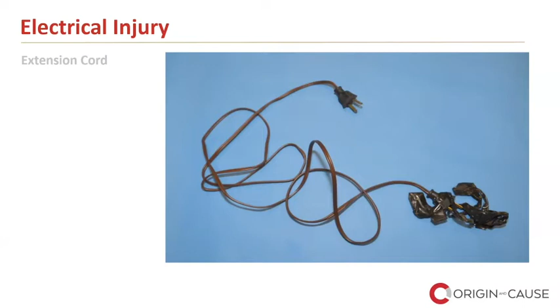The other main use we see for these kinds of cords is to connect generators to house wiring during a power outage. Like I said earlier, if you connect one end to an energized end, say the bottom half of a duplex receptacle, the other will become energized. That works for a generator, and actually on a wider scale than that. If you plugged a generator into your outdoor outlet with one of these cords, the outlets inside your house would also be energized. The big hazard this causes is for utility workers working to restore power during a blackout, because the generator can backfeed into the power lines, and the utility workers can encounter energized lines where they're not expected.